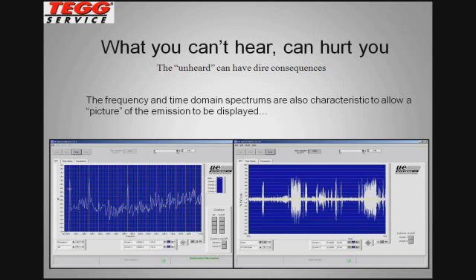When you combine that with the time domain analysis, looking at the right screen capture, with electrical components, in most cases, one would expect to hear nothing. There are a few exceptions, but you would have a broadband or a narrow band of white noise across the time domain if it's functioning properly. The exceptions may be rotating equipment, bearings, transformers, motor contactors, things of that nature. But when we're dealing with circuit breakers and disconnects, switchgear, distribution boards, traditionally they should be totally silent, and you would see nothing in the time domain. It would be just a band of noise.